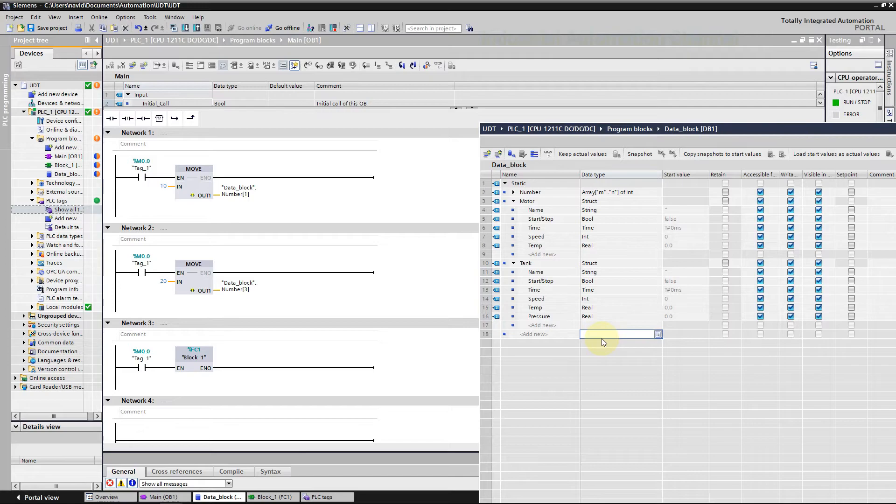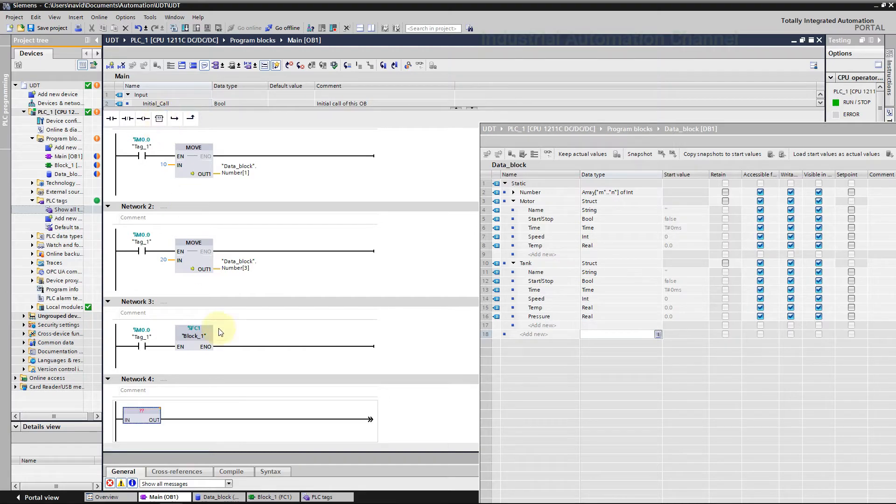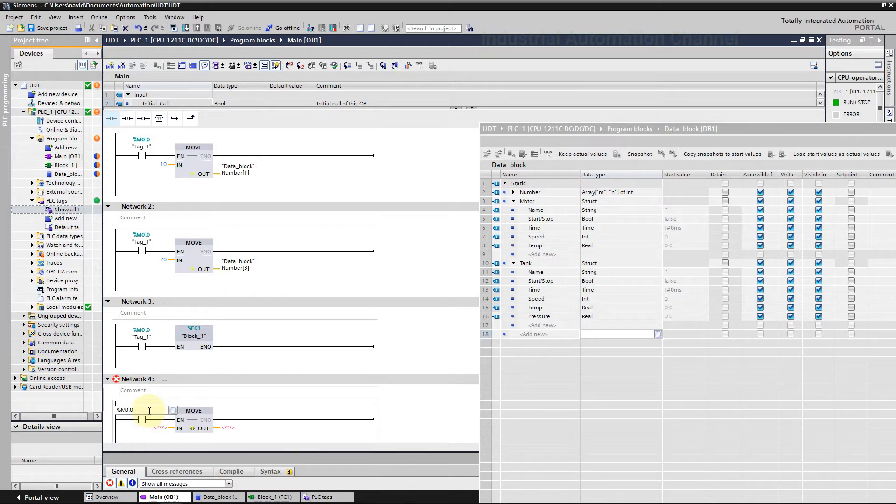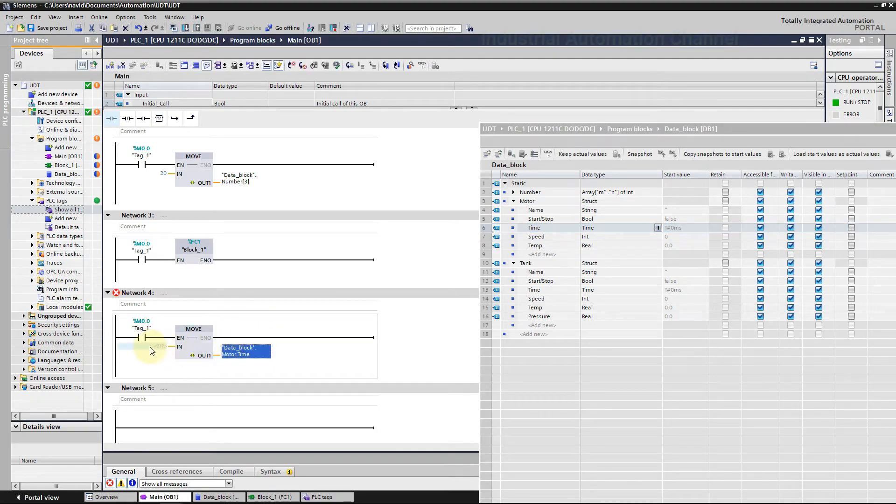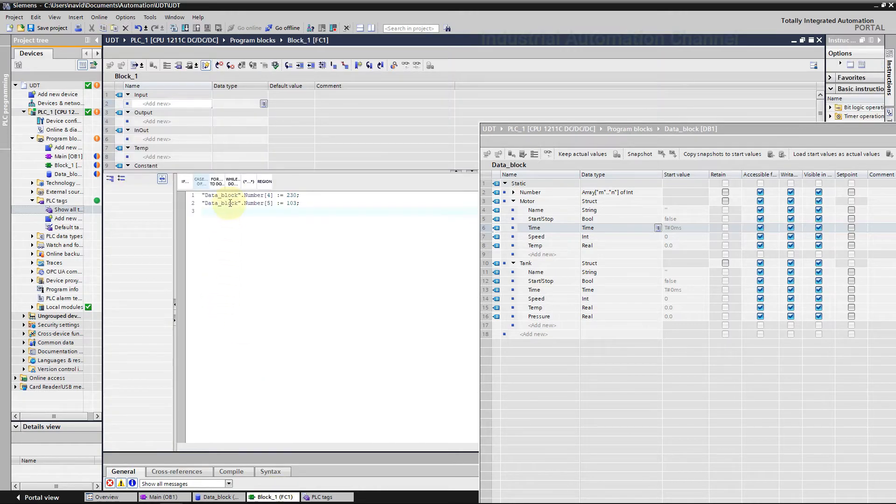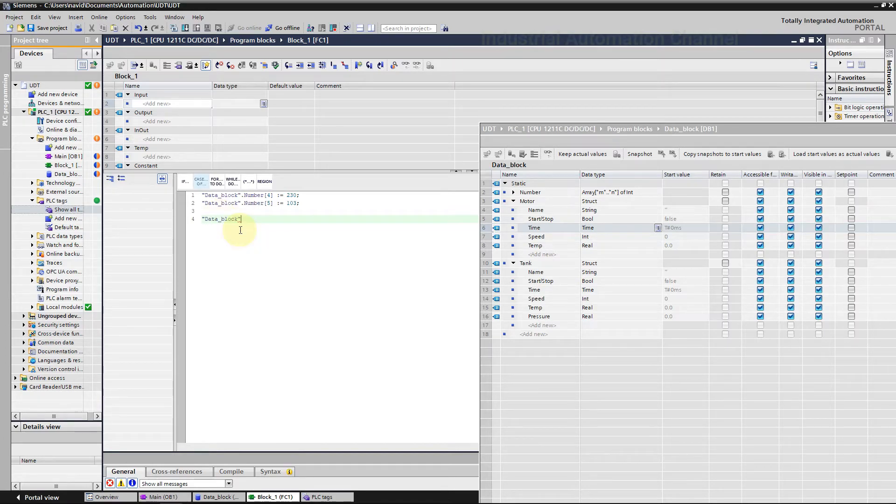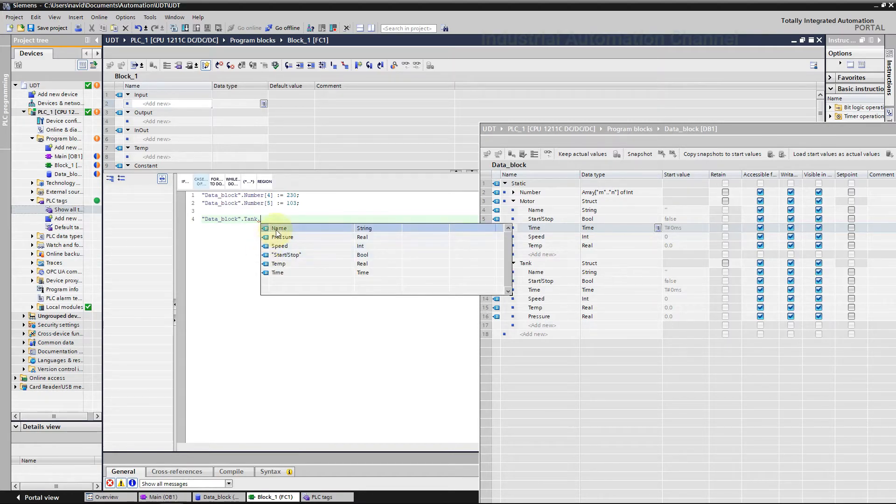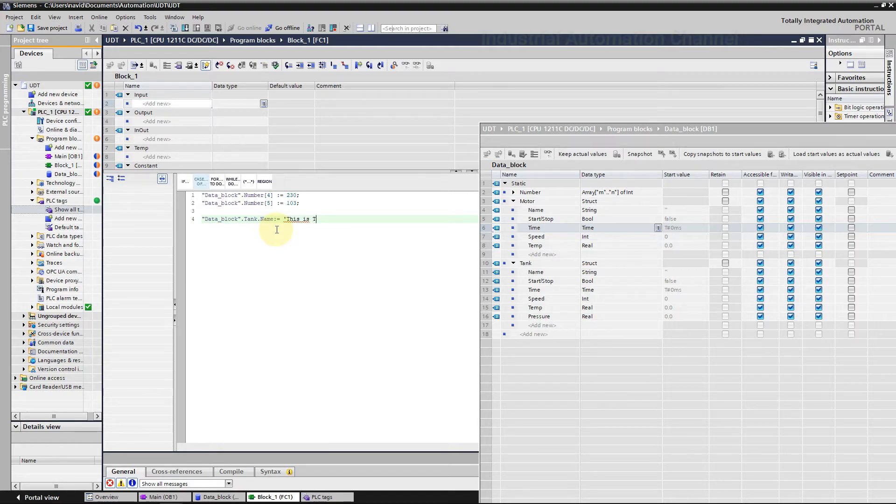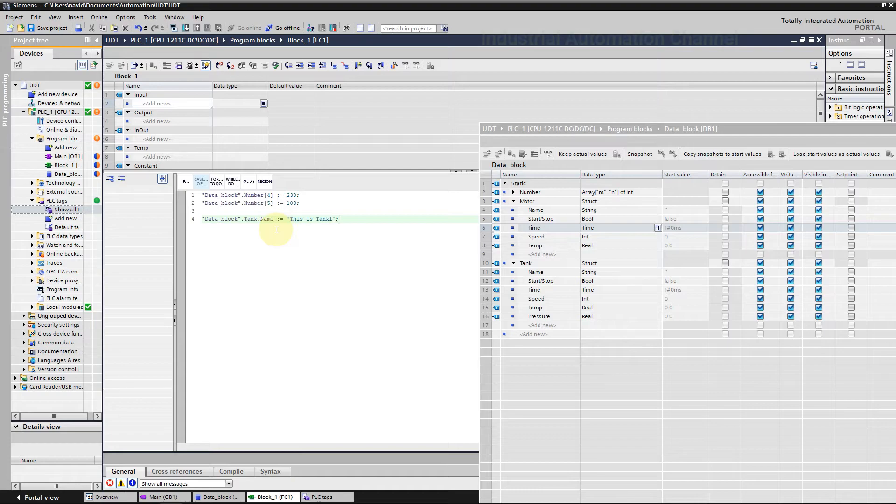As we can see, different data types are contained in the struct data type, each one under a specific category. Access to a structure is like how we used arrays. Create another move instruction, drag and drop the tag here, and in the FC write the data block name plus point, then select motor or tank, again a point and select the variable. With an assignment we can define a name for our tank and define the temperature.